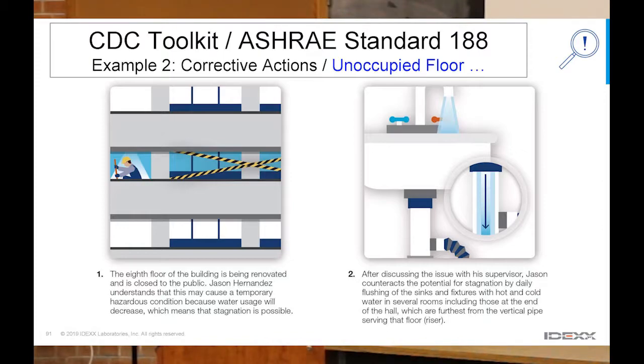Up there it will age. Up there it will be without disinfectant. Up there it will be stagnant. Up there it will grow biofilm. All the things we've been saying. Temperature, be warm; disinfectant, none; flow, stagnant, none; and its use. So this was identified in the risk section, and the control was, when you have a condition of unoccupied, then you'll go down and have a flushing program.